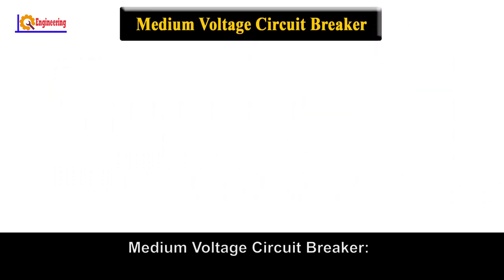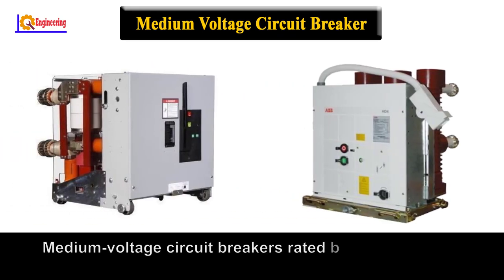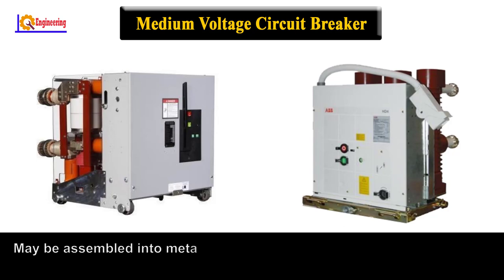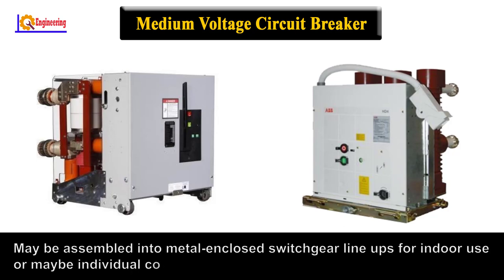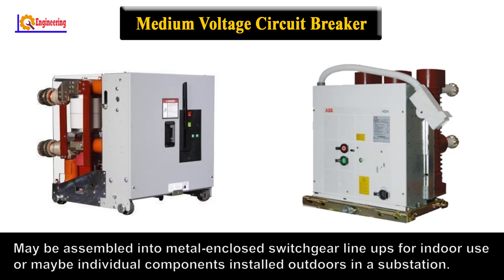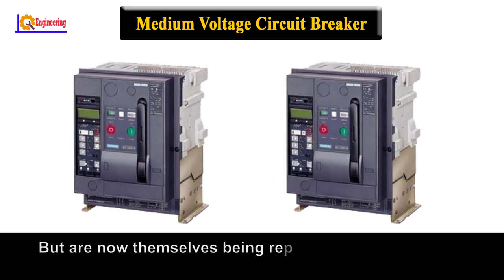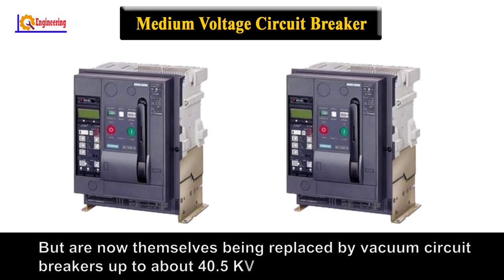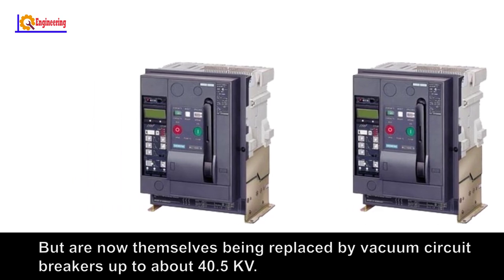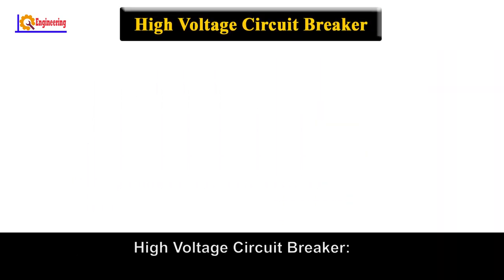Medium voltage circuit breakers rated between 1 and 72 kV may be assembled into metal-enclosed switchgear lineups for indoor use, or may be individual components installed outdoors in a substation. Air blast circuit breakers replaced oil-filled units for indoor applications, but are now themselves being replaced by vacuum circuit breakers up to about 40.5 kV.